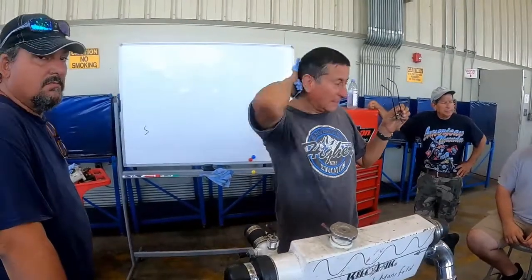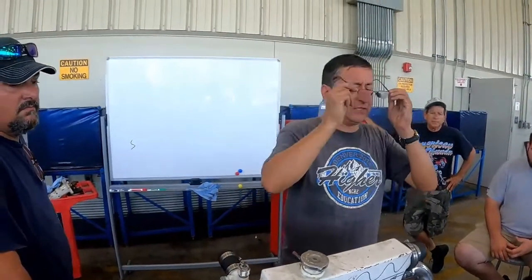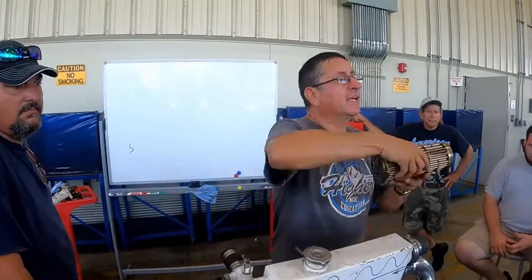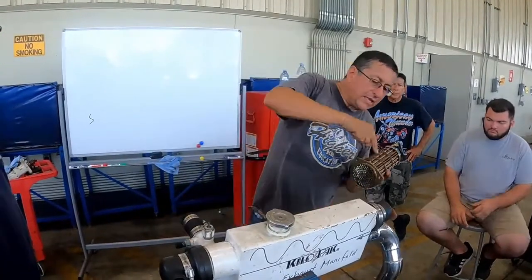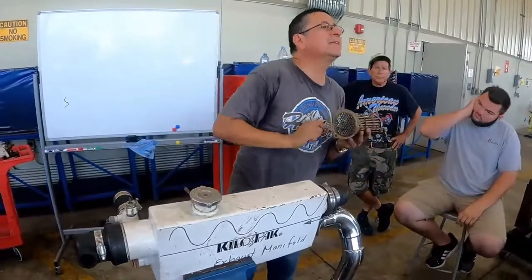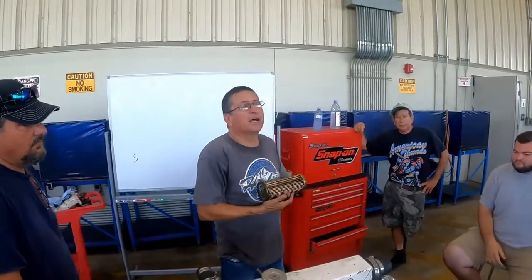So that's why, if you take the coolant sample and you find a lot of nickel, that means that... Correct. If you find that high level of nickel, what is the indication? That you have erosion in this metal. What other element can you find in the coolant sample if this is broken? Silver, because the soldering is with silver. Lead, because of the soldering. Nickel, because of the metal. Copper, of course, because it's copper nickel.